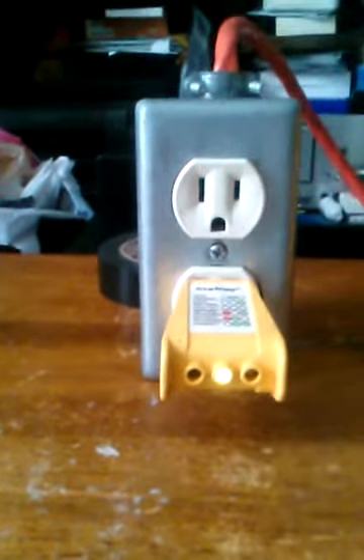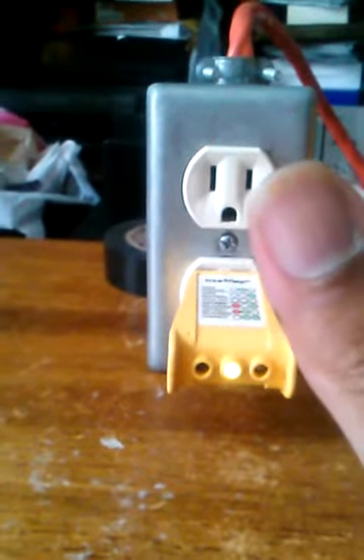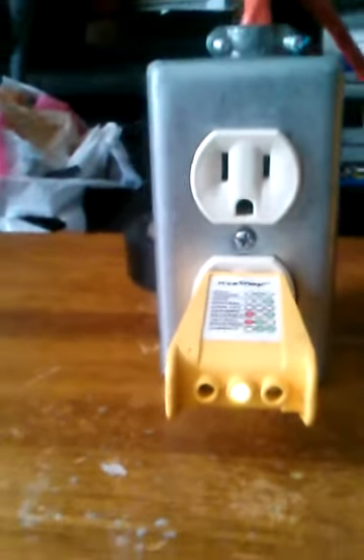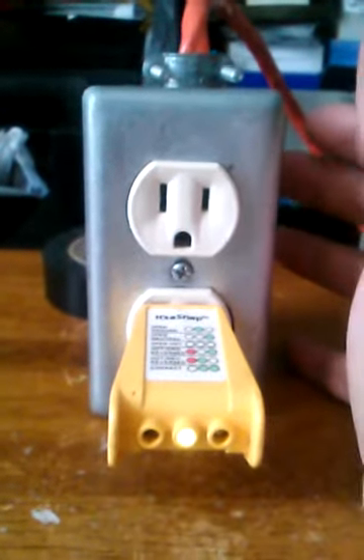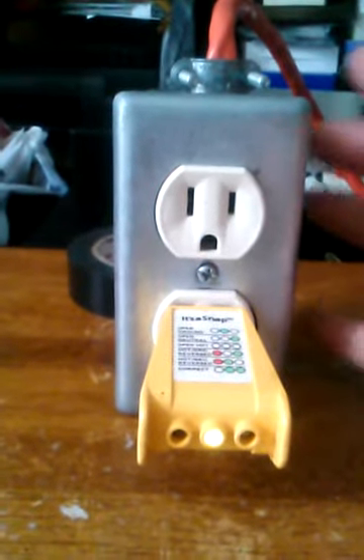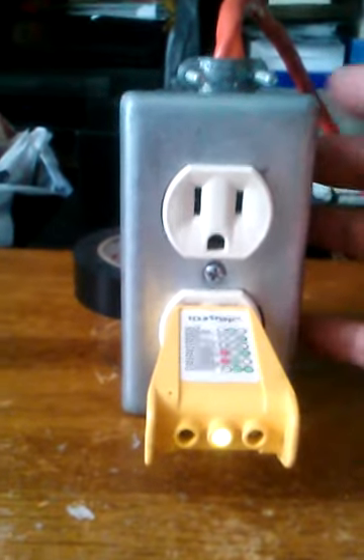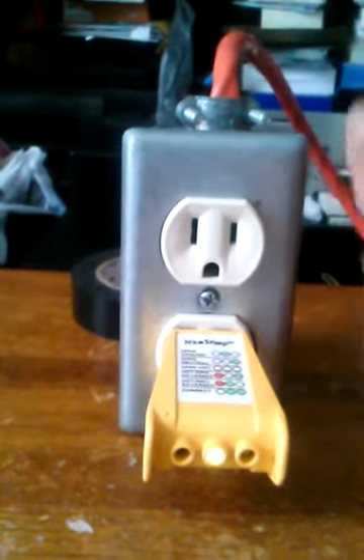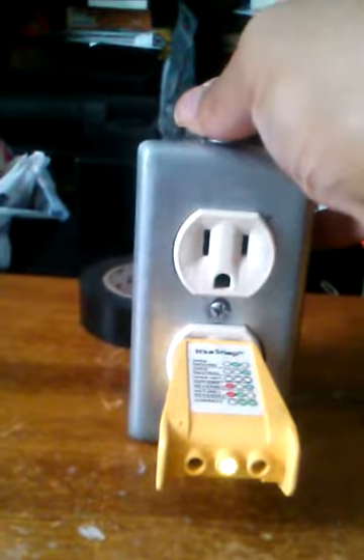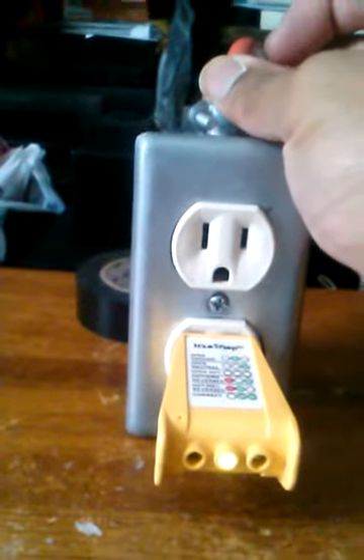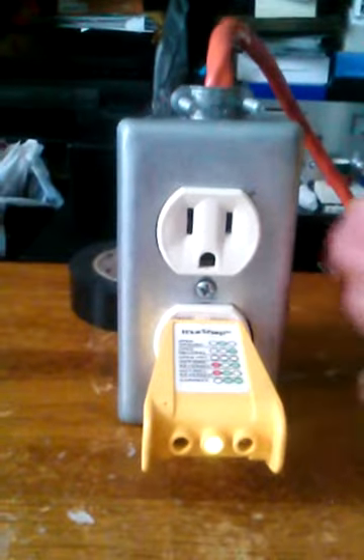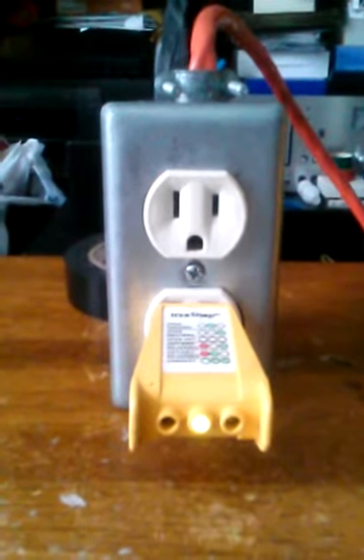That's why I say about grounding and how important it is for computers. You can still use that type of wiring in your building. Just make sure that if you use an armor clad or BX cabling system, that all your points in the electrical system are properly grounded and each connection is super tight, so it can't be taken loose at any given point, or it doesn't come loose by itself because it wasn't tightened down properly.